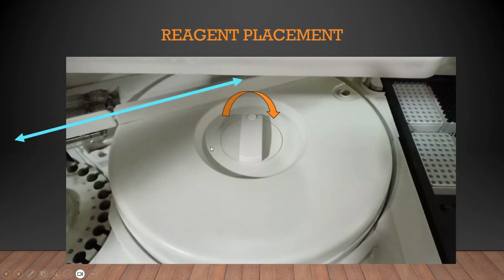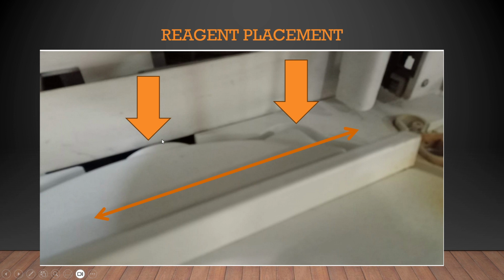Okay, so once you put it, you have to put the cap back. So when you are putting the cap back, you should always look at this straight line. See, many times they try to put it, they don't know where it will fit, they will try to adjust, all this type of nonsense they do. So what you have to do is always remember this straight line, it will always be maintained. And see, this is where the opening and closing mechanism comes, and this is an arrow area where the sensor for the cap is present. So if you direct your cap properly in these two directions and along this straight line, you are able to fit the cap without any difficulty.